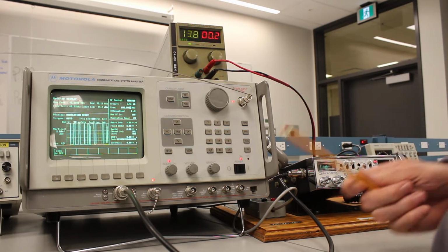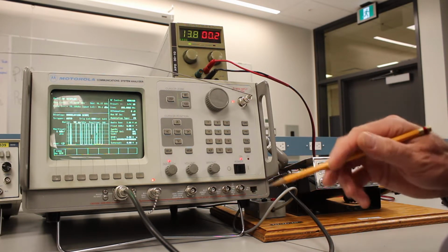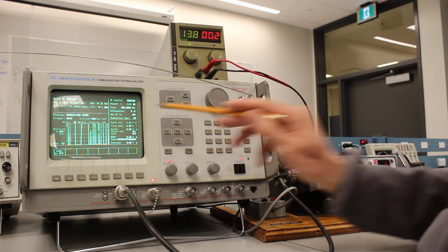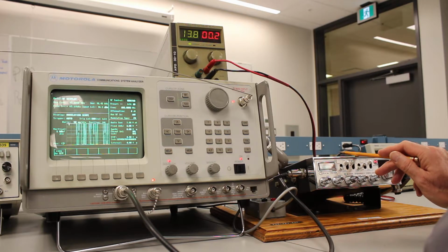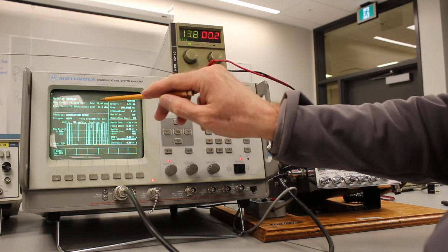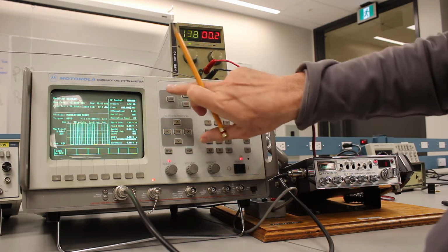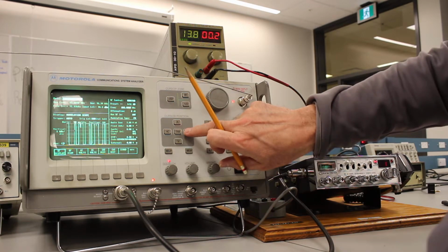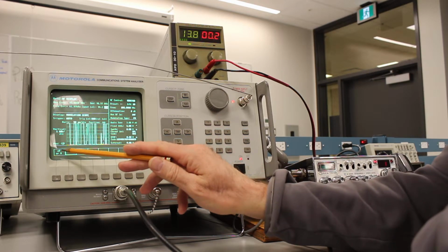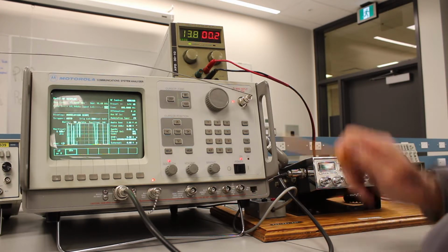But the purpose of this demonstration is to demonstrate the features of this instrument. We would need to tune in the frequency of the radio under test, and we can push to talk, and at that point we will see on the display the input level measured in dBm. We have an option at that point to look at that signal in watts or microvolts, depending on our choosing.